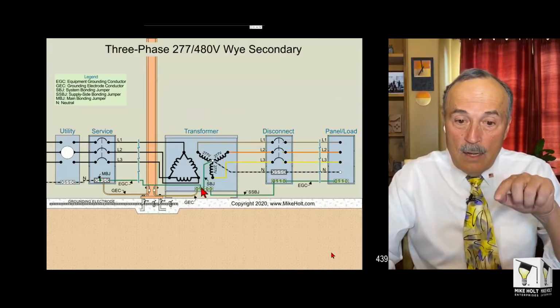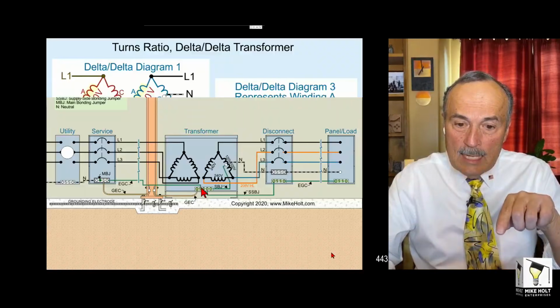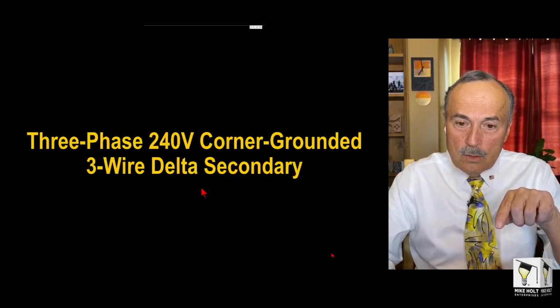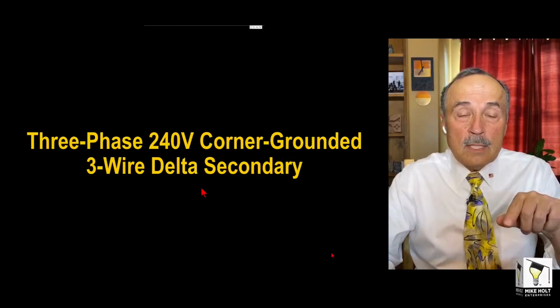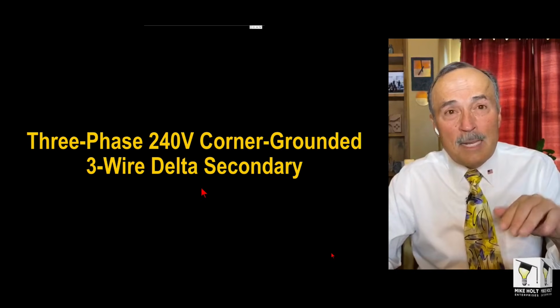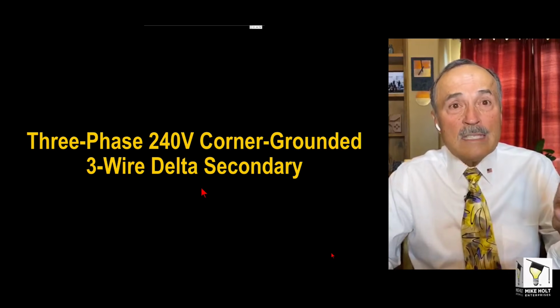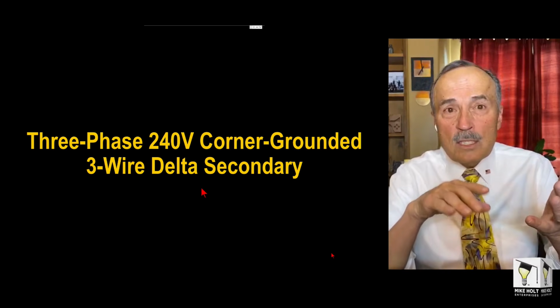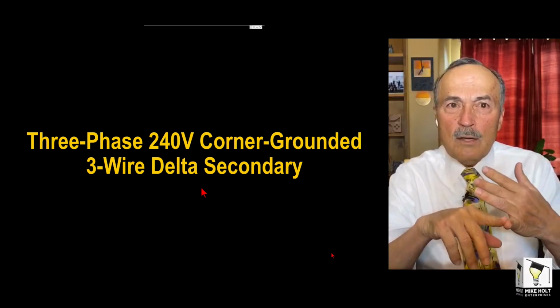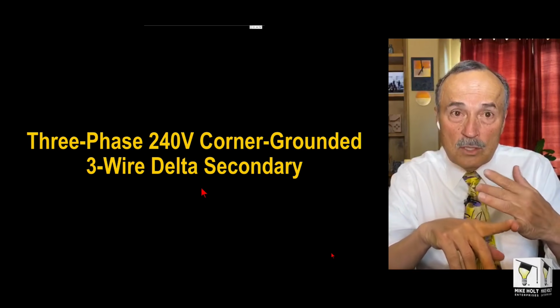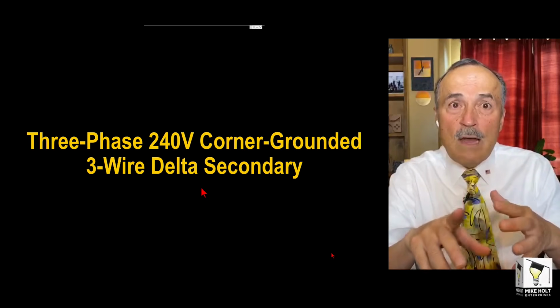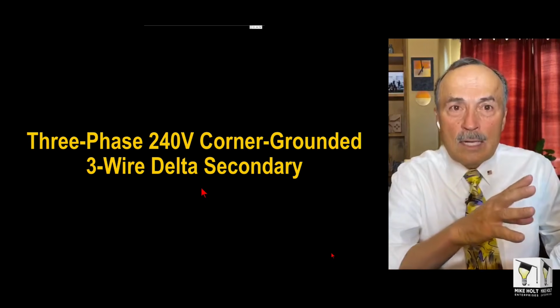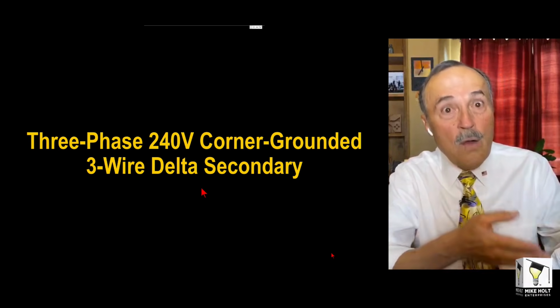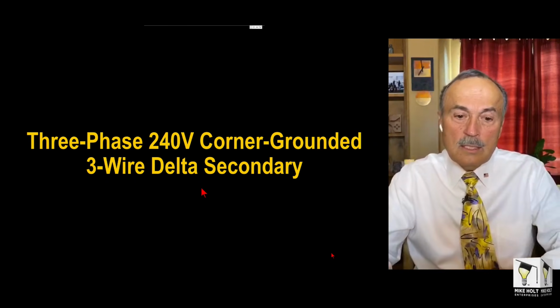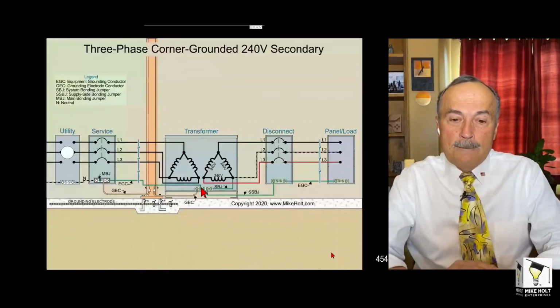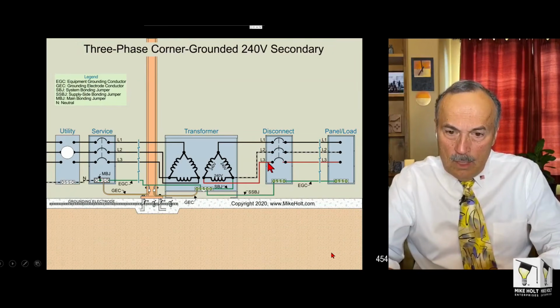All right. We are now going over, we got done with the high leg, and now we're going over a lot of stuff here. Corner grounded delta system. Not that common, but research reminded me, Mike, because of the problems of an ungrounded system, because Beeman talks about 8 or 9 different reasons why you have failures of ungrounded systems and the equipment associated with that, you really want to go with a grounded system. Then they took these ungrounded systems, they just corner grounded them. And so now we're going to talk about, well, how do you do a corner grounded delta system? 3-wire. Okay. Well, you have line 1, line 2, line 3.